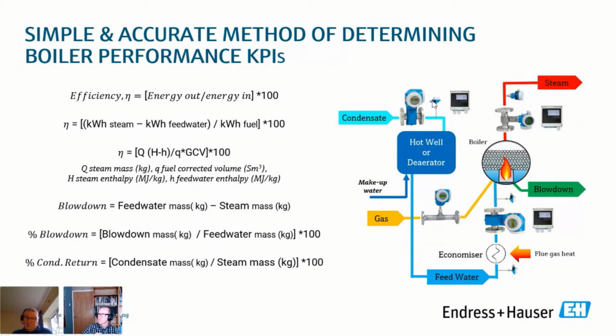And again, the more we get back, the less makeup water we'll need, so the less fuel we'll need to raise the steam. And the more heat we can recover through the economiser, the higher the temperature, the less fuel we'll need to raise steam again. So all of these parameters together give us a little indication of why the fuel to steam efficiency might be just slightly lower.